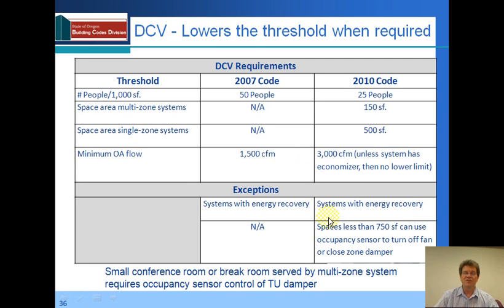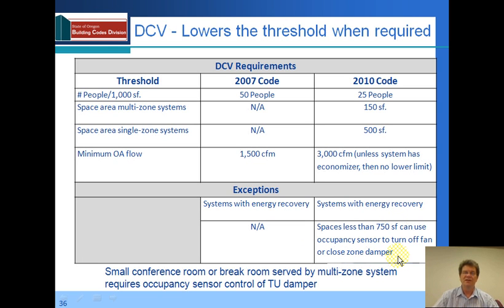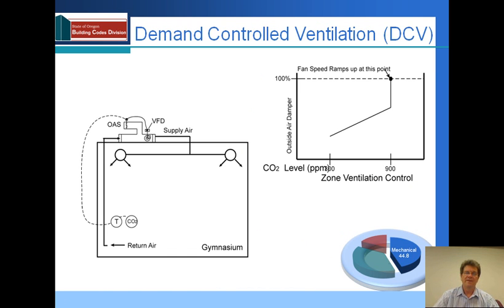One thing to note is that demand-controlled ventilation can be controlled with a CO2 sensor, which senses the CO2 concentration in the room, which indirectly tells the number of people. But if the space is less than 750 square feet, it can use an occupancy sensor to turn the fan off or close the zone damper — a less expensive alternative that still provides good demand-controlled ventilation. In a typical system, you might or might not have a variable frequency drive depending upon the size, but you will always have an outside air damper that is controlled with a damper motor, in turn controlled with a CO2 sensor in the space.